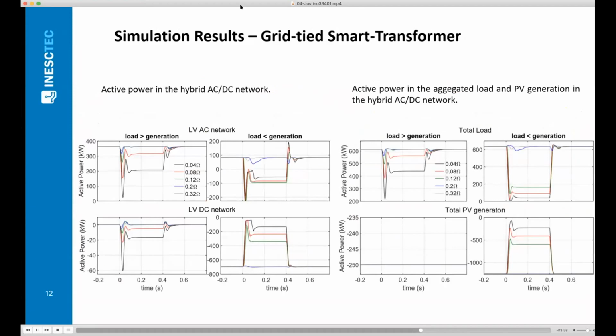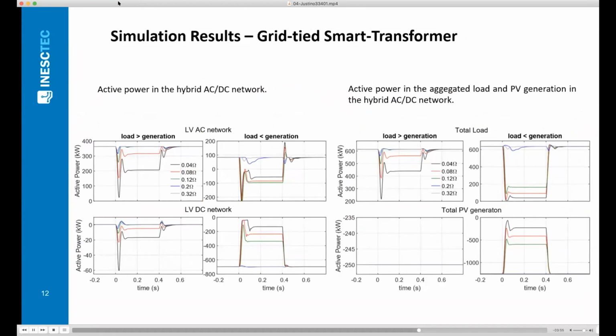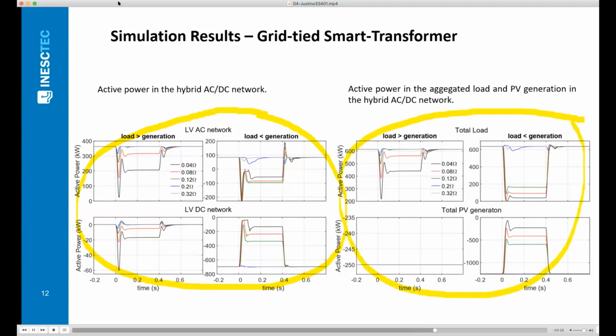The effect of the proposed fault ride-through strategy on the active power in the hybrid distribution network for the considered scenarios is shown in this slide. The different contributions from the low voltage AC network and low voltage DC network are discriminated here. The discriminated contributions of load and generation existing in the hybrid distribution grid are also shown here. It is possible to observe that the most severe power curtailments occur for the faults with lower impedance.